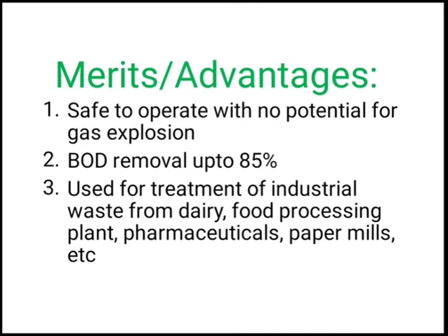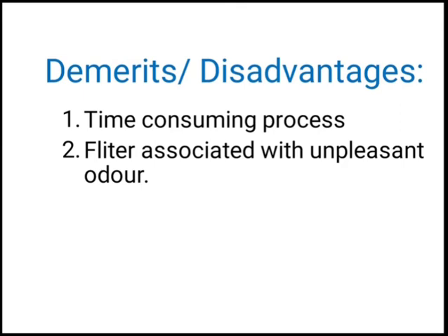Then the BOD removal by this method is around 85%, and this method is useful for the treatment of industrial wastewater from the dairy industry, food processing plants, pharmaceutical industries, and paper mills. So this method is very advantageous. Some disadvantages are also there. This method is a very time-consuming process, and the filters associated with the method have an unpleasant odor. So these are the disadvantages of the trickling filter process.